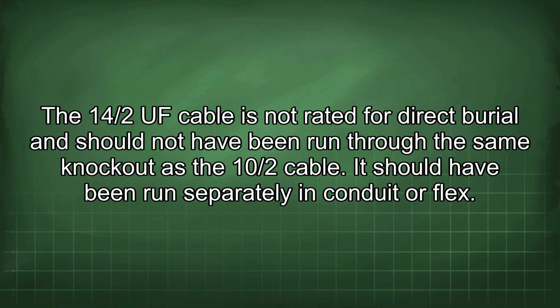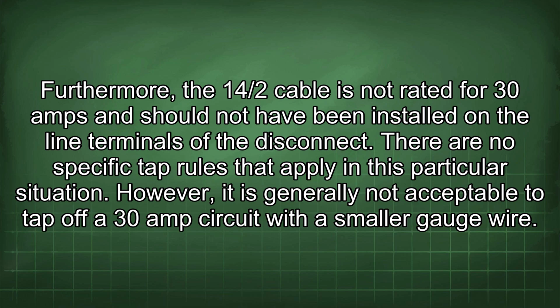The 14/2 UF cable is not rated for direct burial and should not have been run through the same knockout as the 10/2 cable. It should have been run separately in conduit or flex.